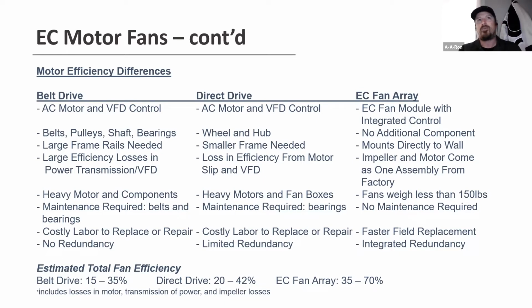So again, we don't have any additional components. The fan is built as one whole complete system. So you don't have belts or pulleys, hubs that are extra wheels. It's all balanced from the factory. You don't need large frame rails. Everything is directly mounted to the bulkhead wall, where you don't need any vibration isolators, cork insulation, anything like that. These are AMCA certified to be mounted directly to a rigid mount. And therefore, you don't have any of that transmission loss. So you save a lot of efficiency without having to wear belt slippage, pulleys, ratios, and things like that.